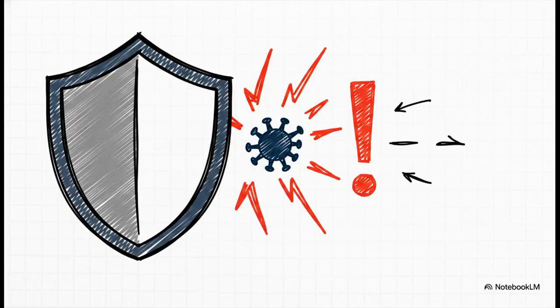The answer is effectively no recovery, set at less than 1 CFU. You simply cannot rely on end product sterility testing to prove safety. Why? Because that test is massively statistically limited. It only samples a tiny fraction of a batch. A contaminated vial could so easily slip past undetected if we only relied on that final QC test. Therefore, your Grade A environmental monitoring is your true sterility assurance. If a viable microbe slips through, your control is compromised, and that demands immediate investigation.